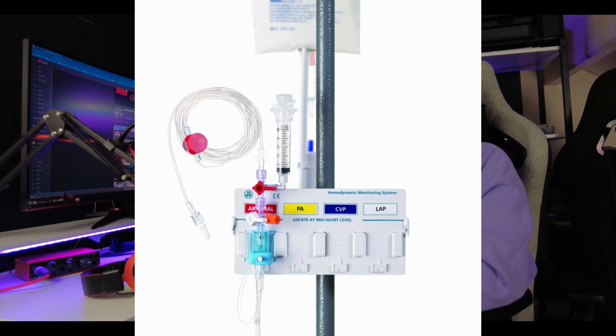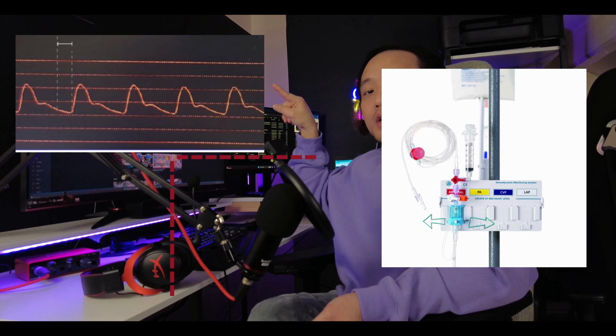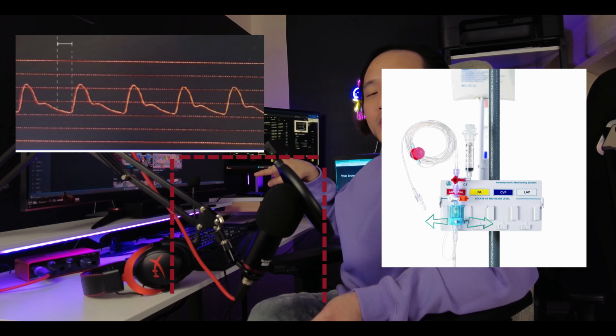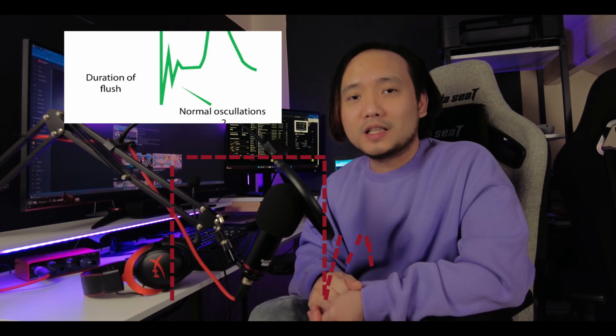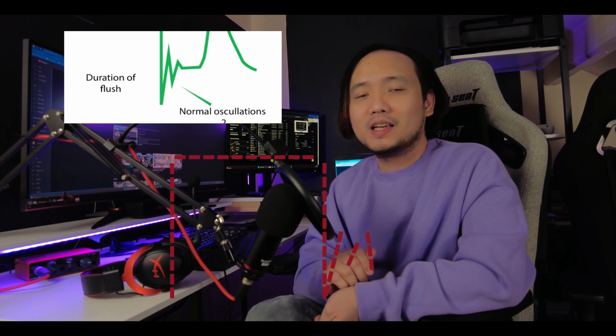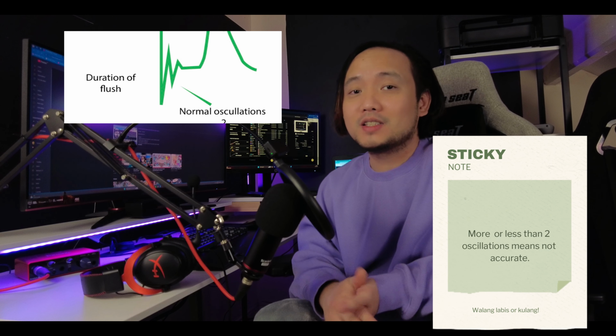Once we squeeze the transducer, the line will just jump up and then it will stay up. But once you release it, there should be a sudden drop. Once it drops, it will oscillate just once or twice. That's how we know it's patent, it's an accurate reading. So those are the two checks that we do to make sure your art line is patent and working well.